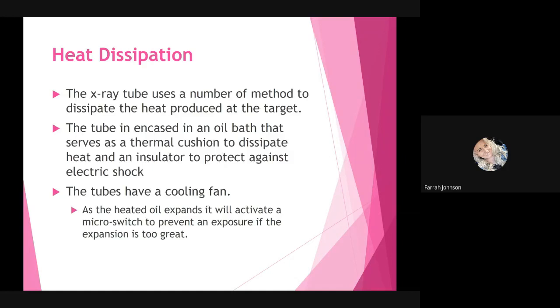The tubes then have a cooling fan, and as the heated oil begins to expand, it will activate a microswitch to prevent an exposure if the expansion is too great. So it's kind of like a safety check-off valve: if the heated oil expands, if it gets too hot, that it might trigger another exposure. This microswitch will basically deactivate it.